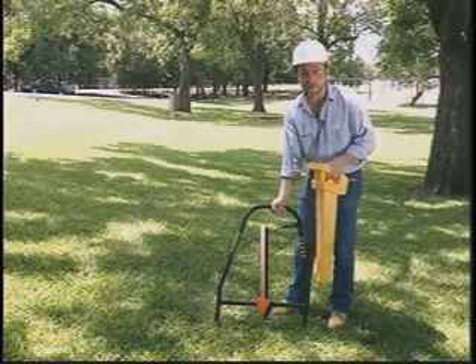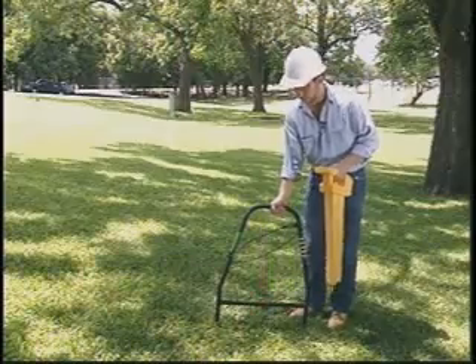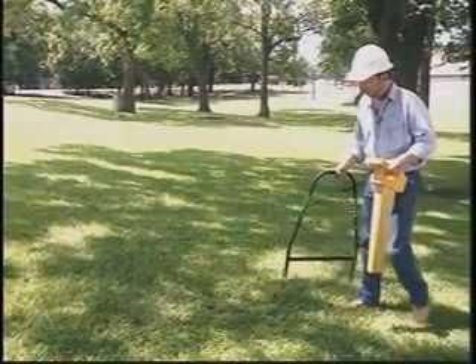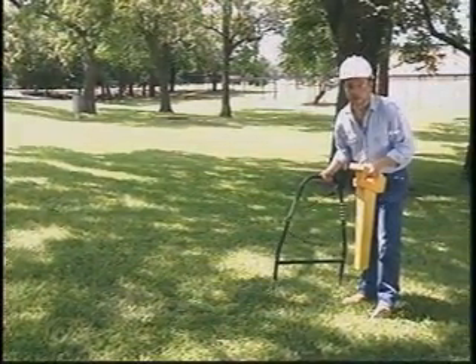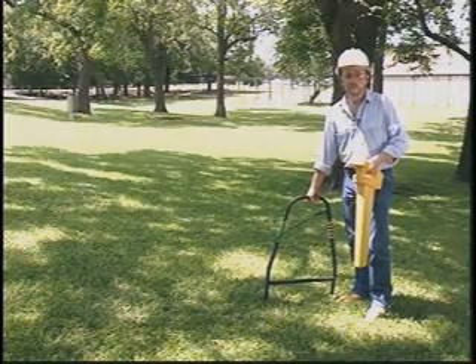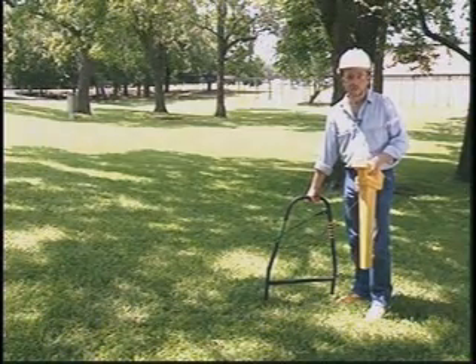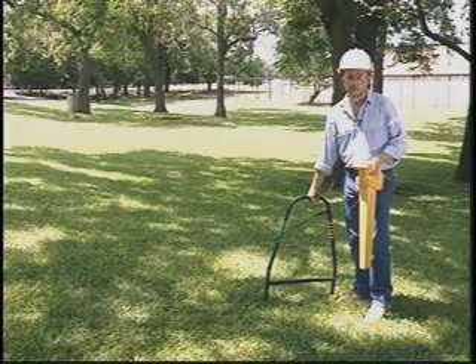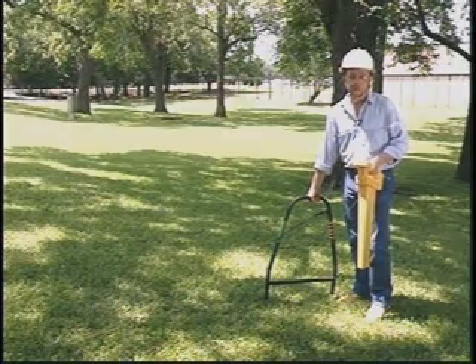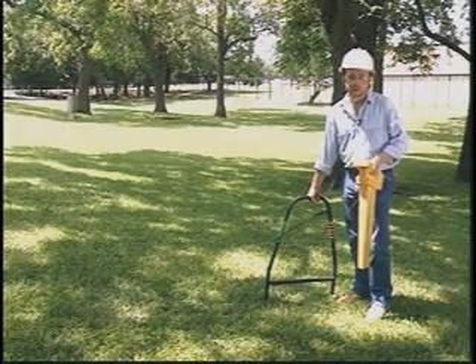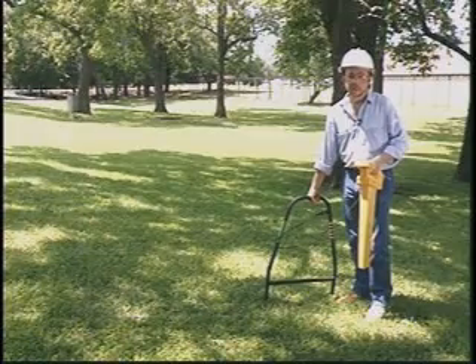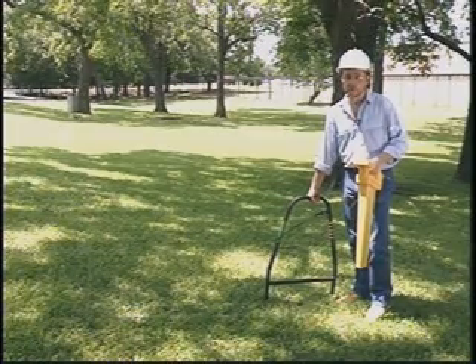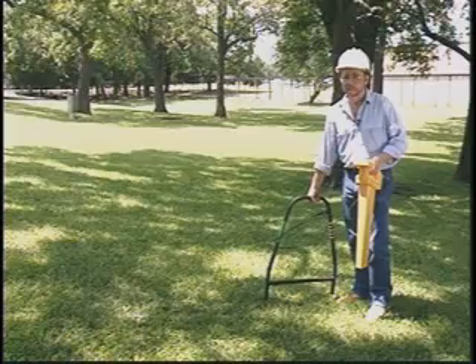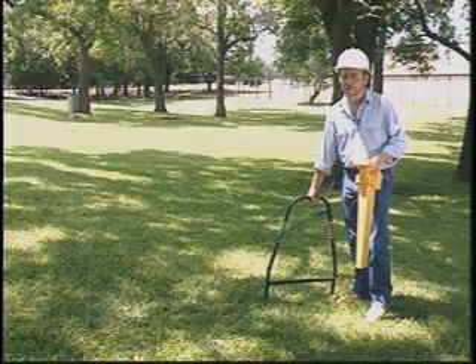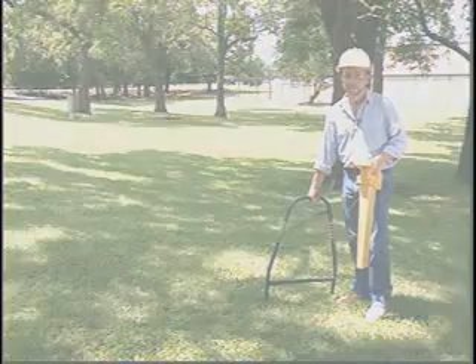You'll now have to determine if this is a major fault. Back up 1 or 2 feet, so the earth contact frame is not over the fault, and compare the fault signal strength to the reference value measured at the ground rod. If the reference value and the fault value are within 20 points, you've located a major fault. If the fault value is less than the reference value by 20 points or more, it's most likely not a major fault, and you should continue locating.